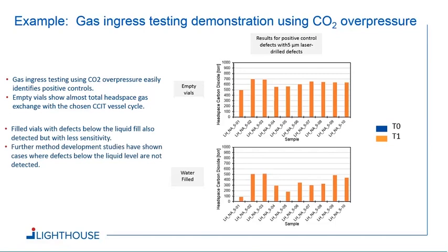And I know that there have been publications showing that if you have a product, for example, a high density proteinaceous biopharmaceutical product, the large proteins can actually clog a hole. And so you have a defective container with an integrity breach, but because something blocks or clogs the hole, a CCI test method that depends on gas ingress or gas flow in and out of the container will not detect that, because the blockage blocks the gas flow. But that's just an example of why robust CCI method development is critical.